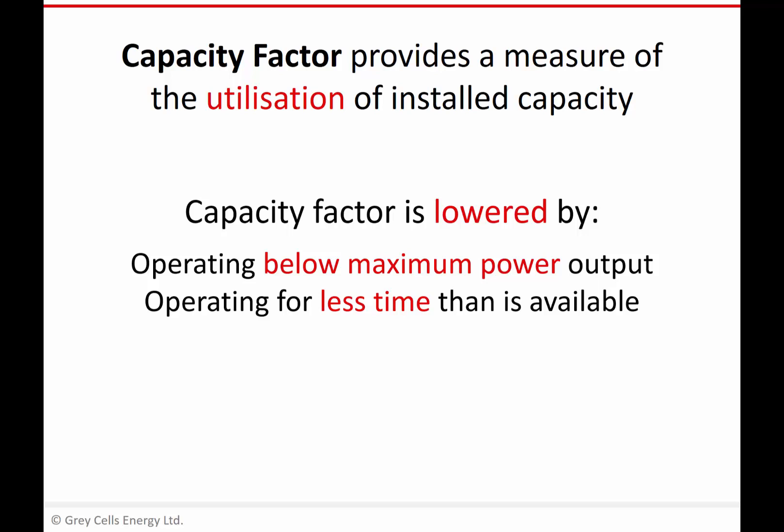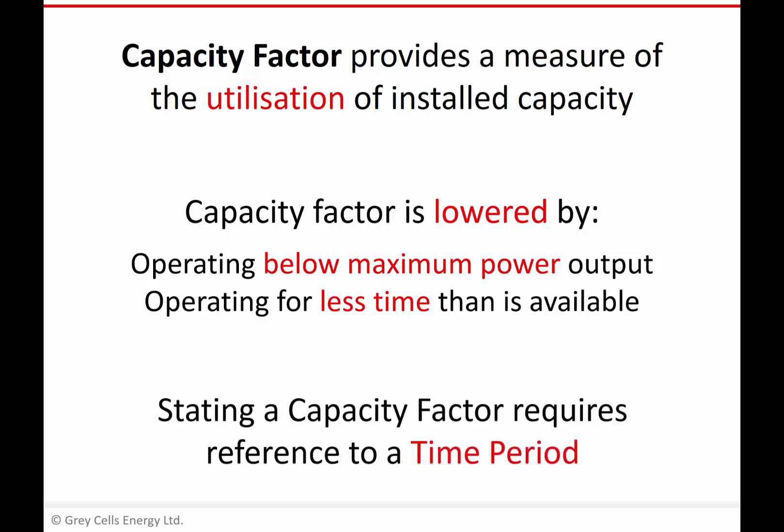Capacity factor can also be reduced if the plant operates for less time than is available — which is what the concept of full load hours captures, where full load hours are fewer than the total hours in the period. This might be because the plant is down for maintenance, has broken down, or in the case of a wind farm, there's simply no wind. In practice, capacity factor is lower than 100% due to a combination of both effects: operating below maximum power and having some downtime. You do need to reference the time period over which you're measuring or calculating capacity factor.